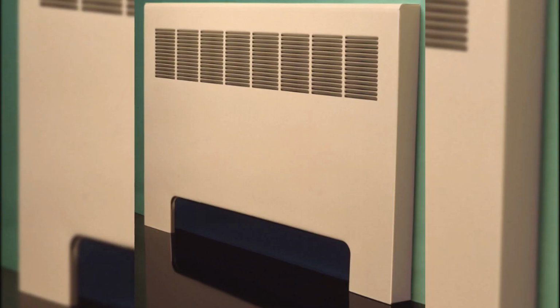6.2.6. The design requirements for HVAC convectors and enclosures. These requirements are applicable to new construction, major modernizations, and capital improvement projects, CIPs. Here are the key design approaches for different areas. 1. Corridors, stairway landings. A. Fully recessed electric convectors or electric cabinet heaters mounted 4 inches above the finished floor can be used.